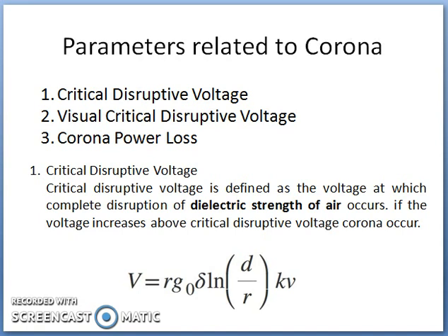We have seen what is the phenomenon of corona and when it appears around the conductor. The corona effect takes place when the applied voltage exceeds a particular value called the critical disruptive voltage. As this voltage increases, the glow and hissing noise also increases. If the voltage increases up to the breakdown value of the air, then flashover takes place.